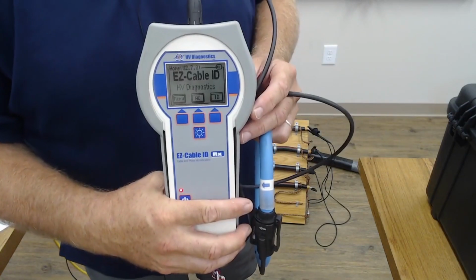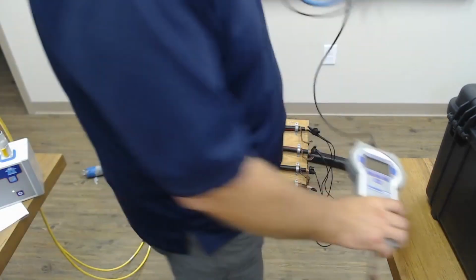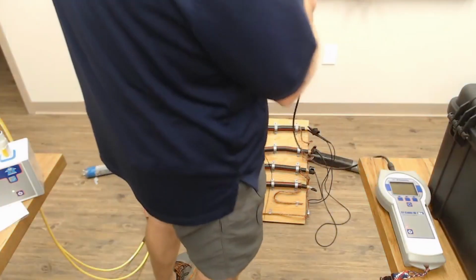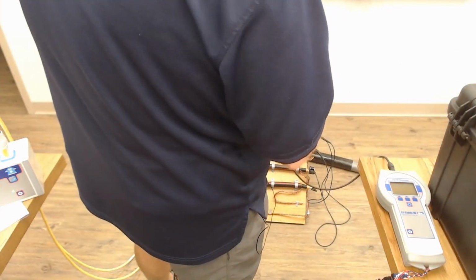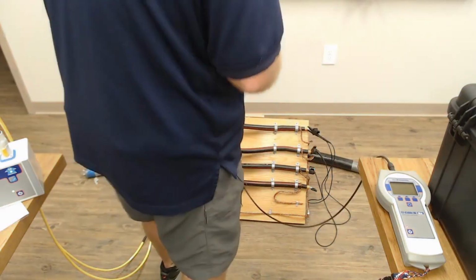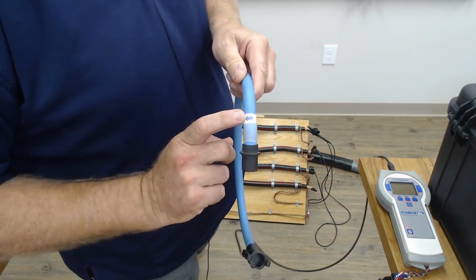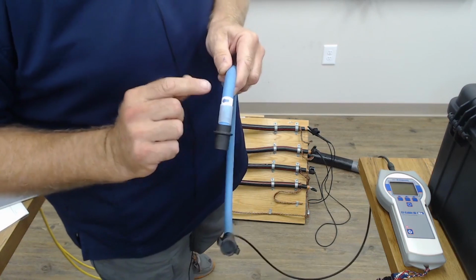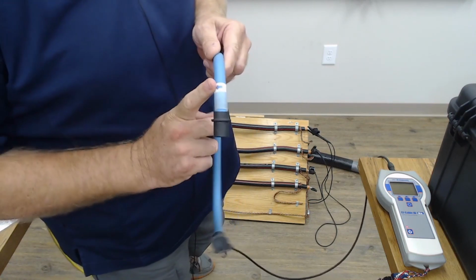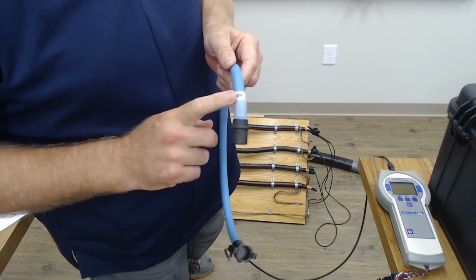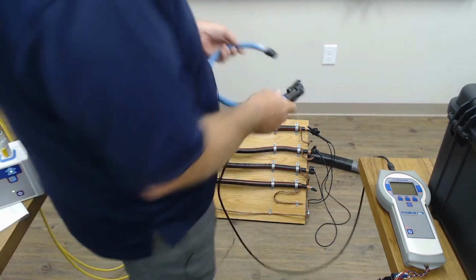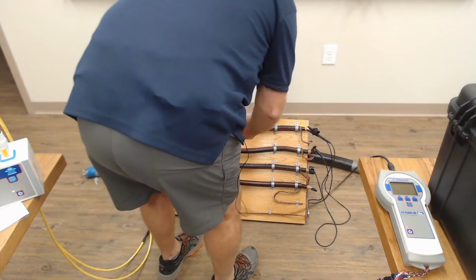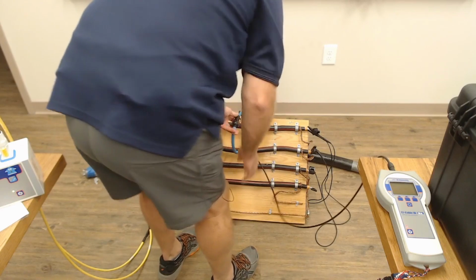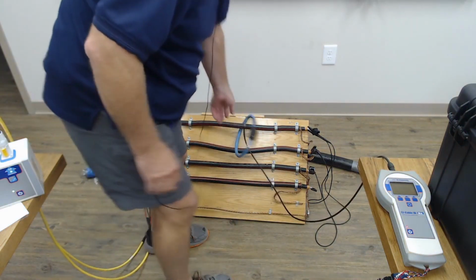Receiver, that's the first screen. What we're going to do is connect first onto our cable that we believe to be one of the right cables. We make sure that the arrow is in the right direction. Some utilities face us towards the transmitter, some face it away. In our case, we're facing it away right now. So that's what we make sure is the arrow is in the correct orientation. So you can see the arrow down below there.